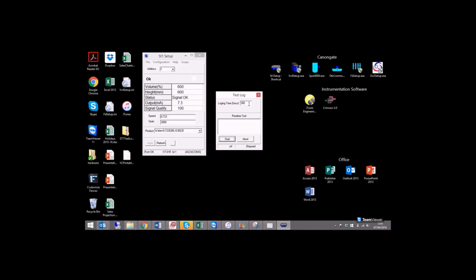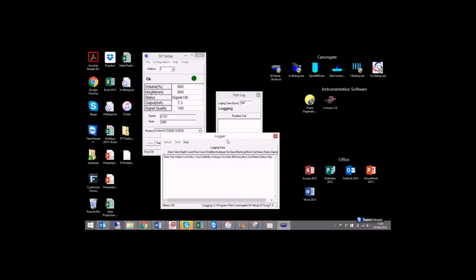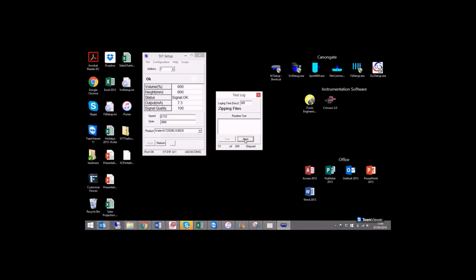So, logging time in seconds. Typically, if the problem is there and in front of you, 5 minutes is enough, 300 seconds, but this can be extended as long as you want, really. Just a note that you can't use any other aspects of the software while a support file is being created. So we click Start. I'll open the logger, and every few seconds or every second it will log the settings, and it'll do that for 300 seconds or until you abort it, whichever comes first. So to save us 5 minutes, I shall abort.